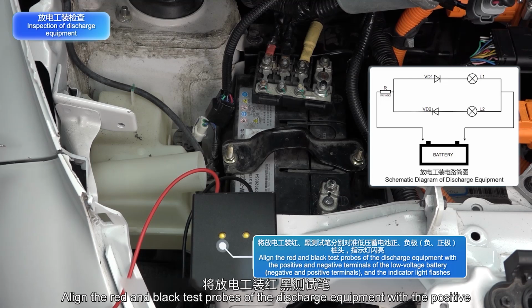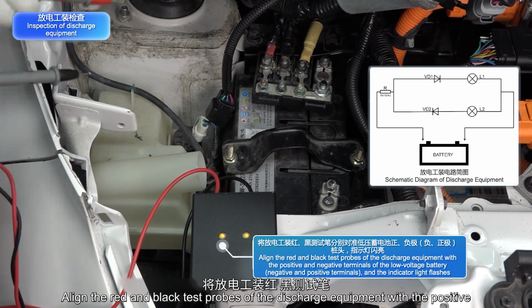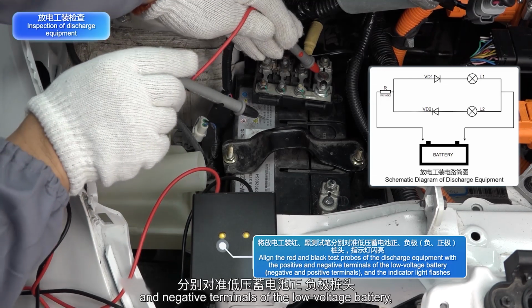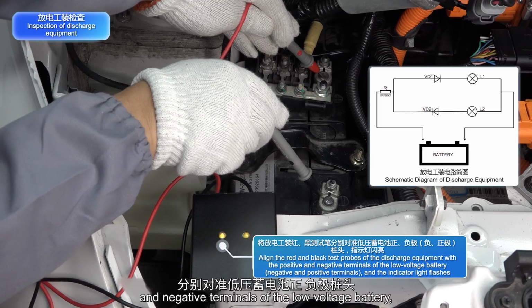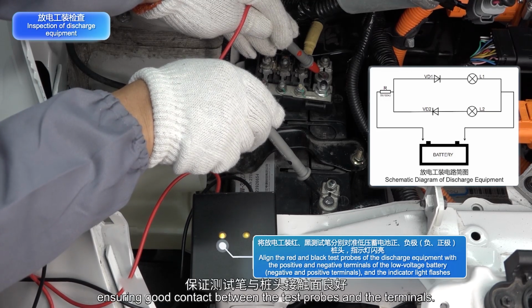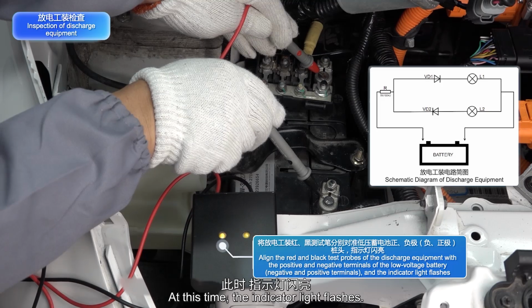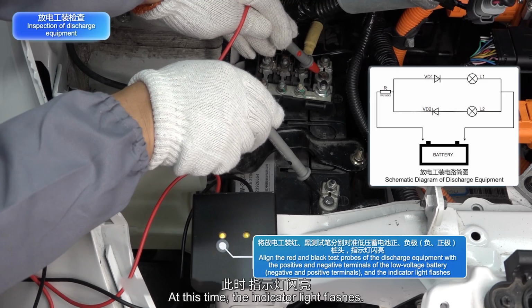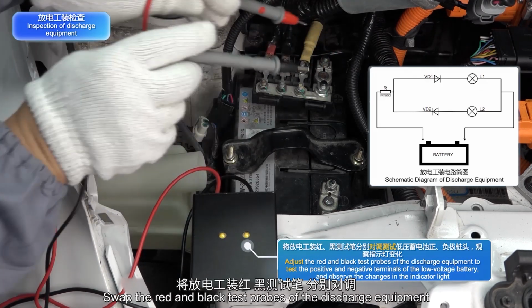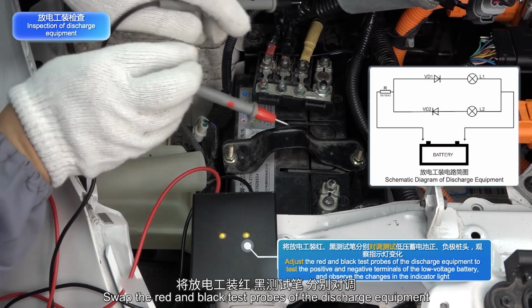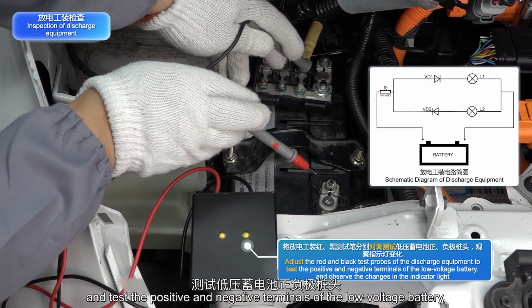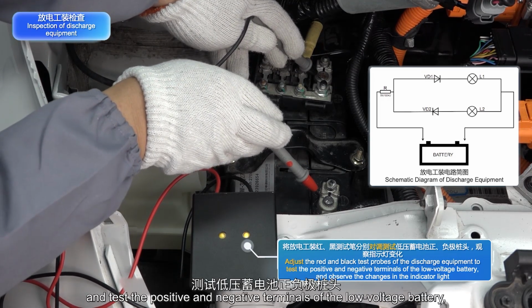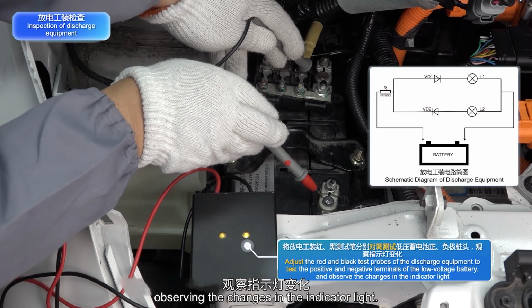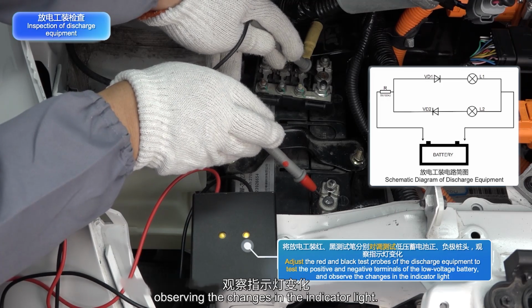Align the red and black test probes of the discharge equipment with the positive and negative terminals of the low-voltage battery, ensuring good contact between the test probes and the terminals. At this time, the indicator light flashes. Swap the red and black test probes of the discharge equipment and test the positive and negative terminals of the low-voltage battery, observing the changes in the indicator light.